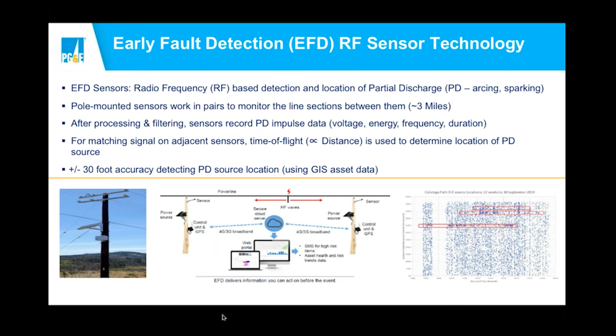If you go to the next slide, there are many ways to analyze this data coming from EFD sensors. What you see here on the left, that chart tells us where the disturbance is observed locationally and at what time and day. The bottom left chart tells us the magnitude of the detection energy. And on the bottom right chart, that tells us which phase the faults are occurring on. Combining all this data, you can get very granular in telling our troubleman which pole to go to and what to look for.